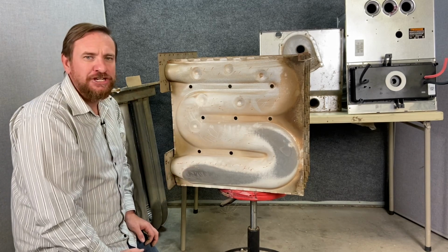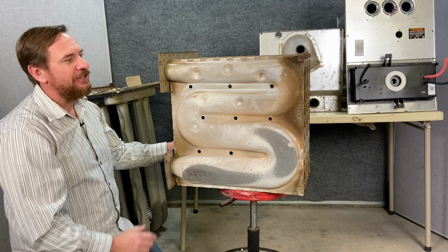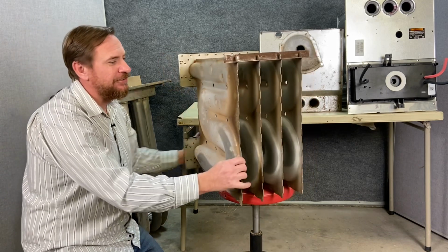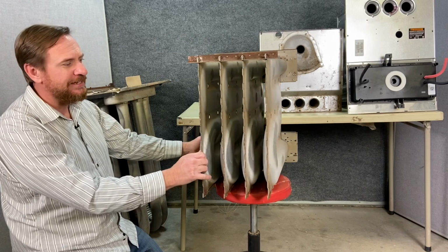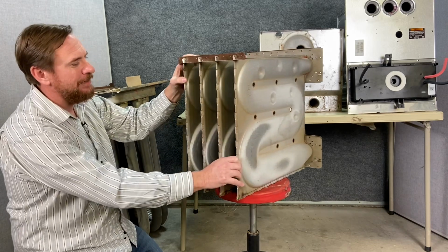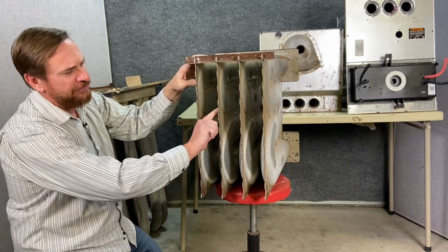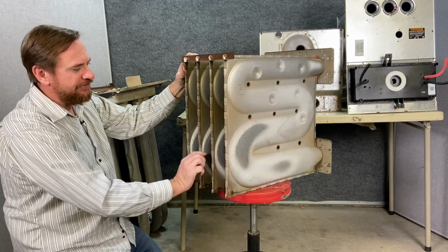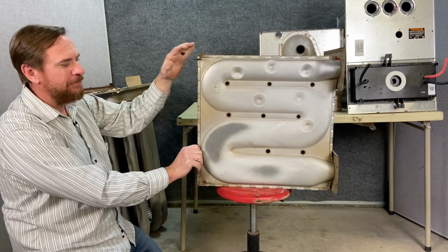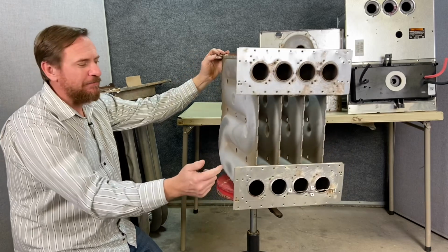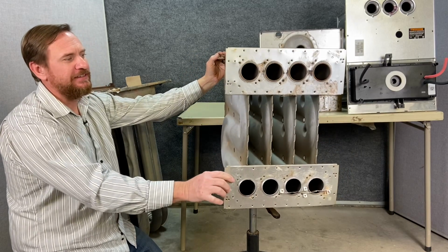A heat exchanger that was well maintained, had a proper combustion analysis in its life, was going to last a lot longer. But this is a little different style heat exchanger. It still worked the same basic way. This was from an 80% gas furnace. We see there's a little bit of rust right here. I don't see any visible holes in this, but I need to really run a camera through each of these tubes to really check this out.